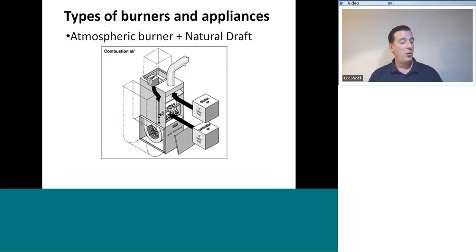Remember earlier when we said that water vapor was a common and normal byproduct of combustion? Well, that's true. It's also true that when the combustion products, or the flue products as we like to call them, cool to the point where they reach the dew point of that water vapor, condensation will occur in the flue, and that can lead to rusted out flue pipes. If the flue is made of brick or masonry, it will corrode and eat away the brick and the masonry. Even if it's a clay tile liner, it will corrode that liner. The combustion products and the water vapor associated with that are slightly acidic, and they will eat away stone and masonry products.